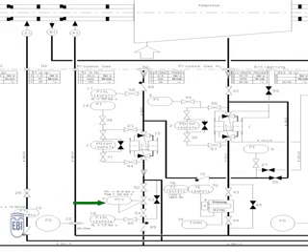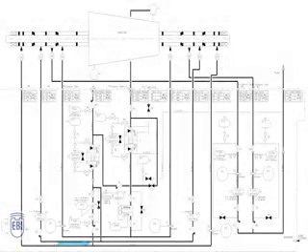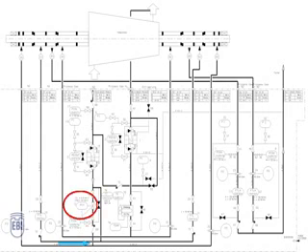The barrier gas flow through the sealing system. To supply with buffer gas, nitrogen is taken from the barrier gas module downstream the pressure control valve. This pressure is adjusted by a pressure control valve and is 1.5 to 2 bar above the high alarm of the flare pipe.